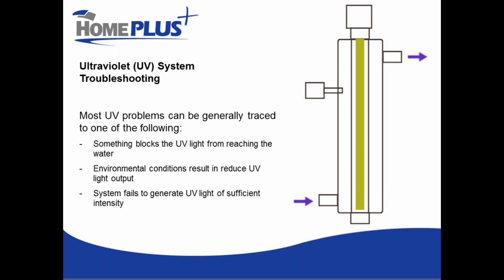So the heart of the system is an ultraviolet generating lamp, and the UV light emanates out from that lamp, passes through a quartz glass sleeve. In my picture here, the lamp is the yellow thing in the middle. The quartz glass tube is the rectangular box around it, and then between that box and the outer part of the chamber is where the water flows. So the light has to pass through a little bit of air, then it passes through the quartz glass sleeve, then it has to pass through the water and ideally reach the outermost part of the chamber.